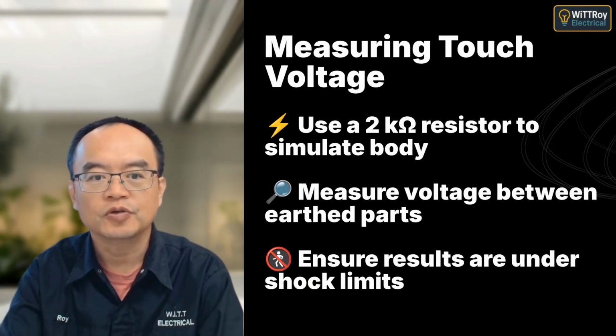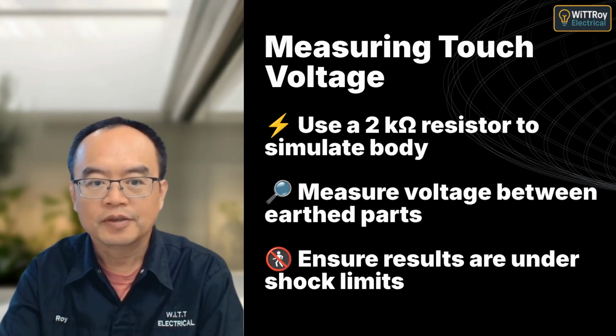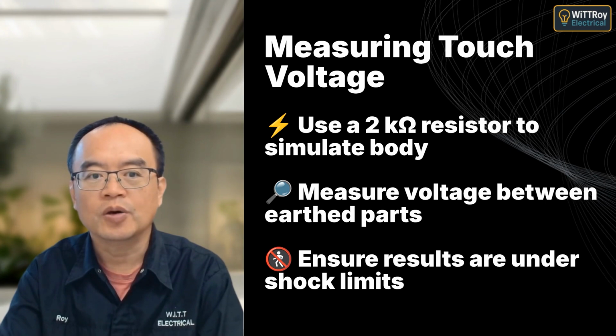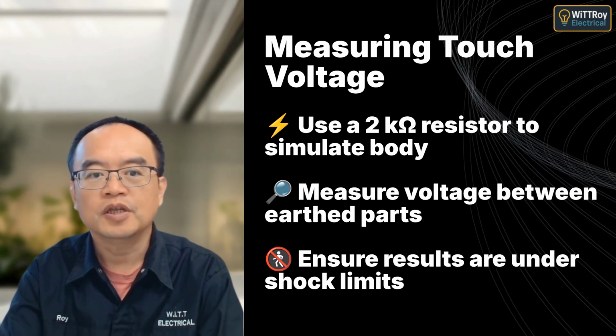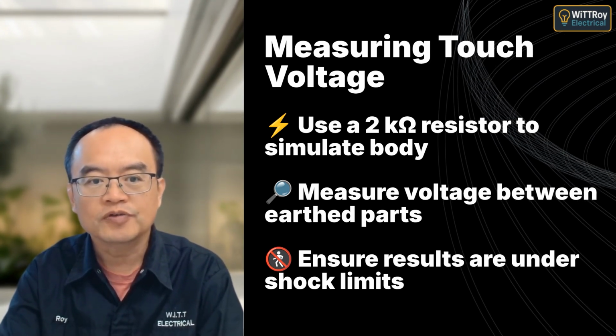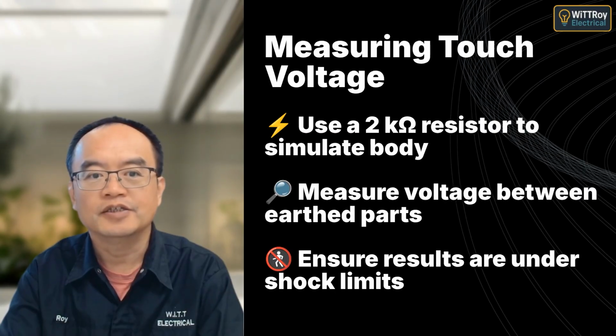To ensure touch voltages are within safe limits, simulate body resistance using a 2kΩ resistor and measure across exposed conductive parts. Ensure readings fall within values allowed in AS/NZS 3000.